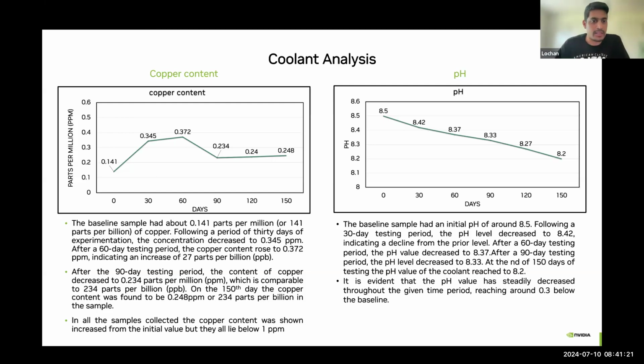After a few days of testing, we see a rise in the copper content level for the next 30 and 60 day period. After that, it drops back to 234, and it stays in the range of 240 parts per billion for the next 90 days of testing. The overall observation was that the copper content never increased above one ppm in the whole coolant. It states that there was almost no loss of copper from the cold plate.